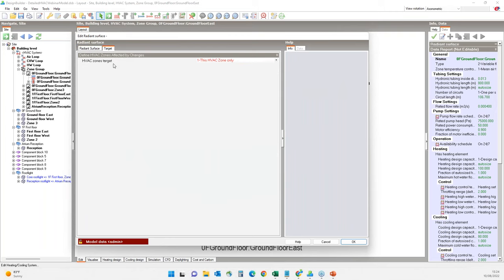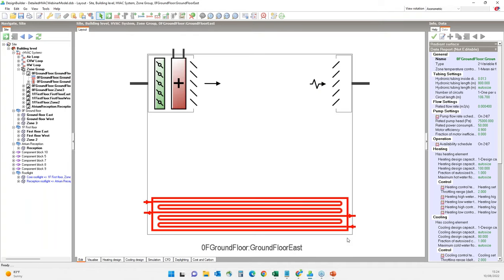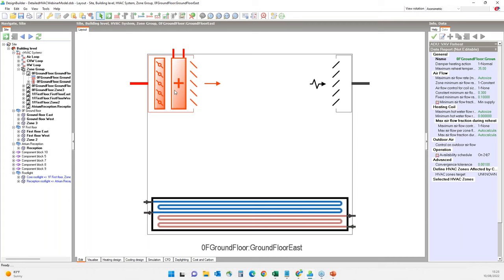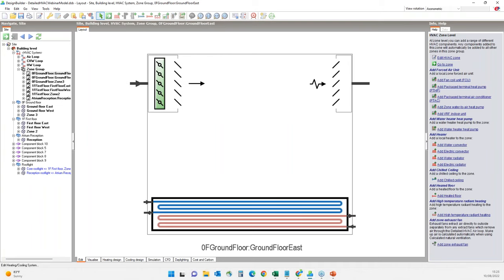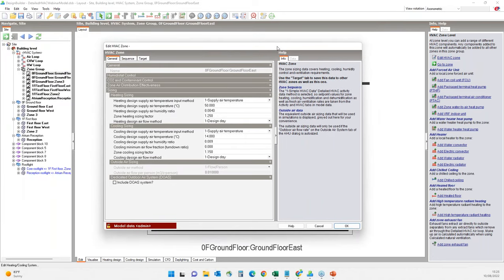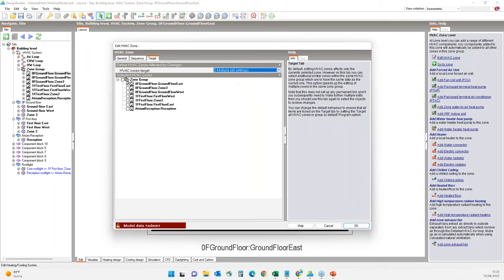I'll add the radiant surface object, which has both heating and cooling pipes in one component. I'll change the number of circuits to 'calculate from circuit length' — the recommended setting. The default length is 106.7 meters (350 feet), which is the maximum circuit length allowed in Title 24. I'll apply this setting to all radiant surfaces. Next, I need to change the air distribution unit, removing the reheat unit and replacing it with a VAV unit without reheat. Because we are modeling a dedicated outdoor air system, I need to enable the 'include DOAS system' checkbox for correct heat gain/loss calculation, and apply these settings to all zones.